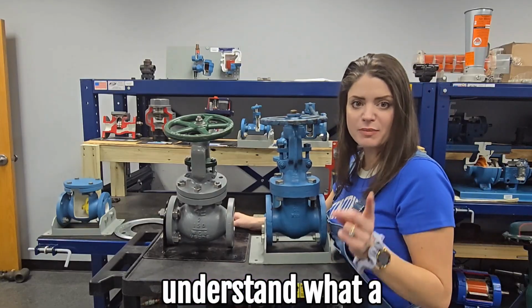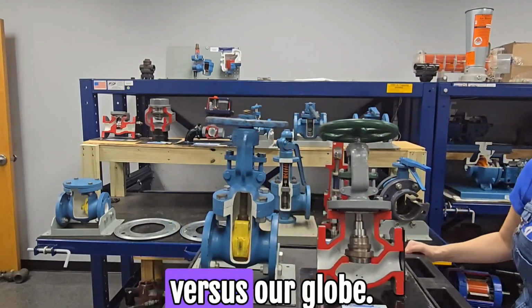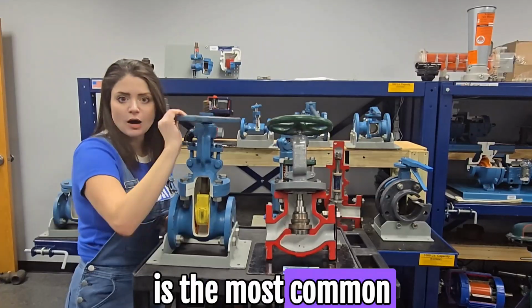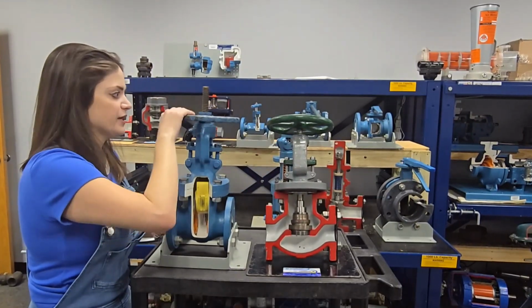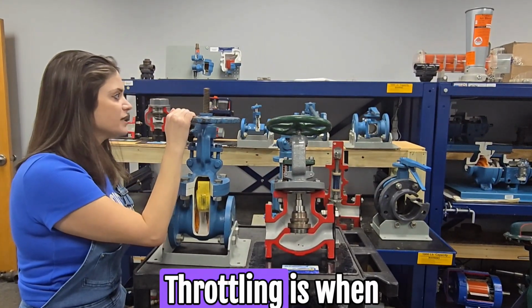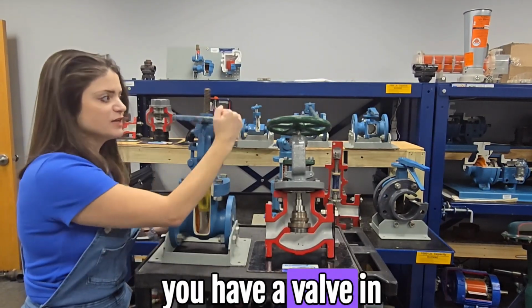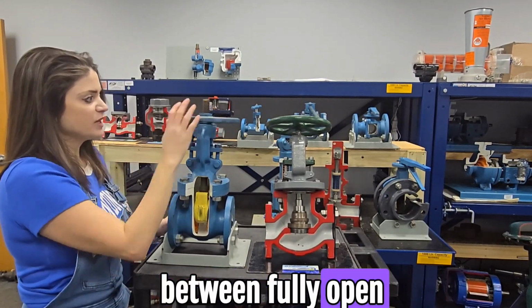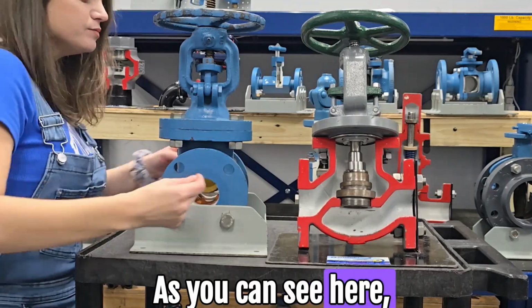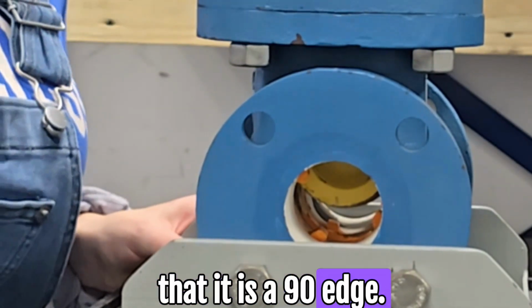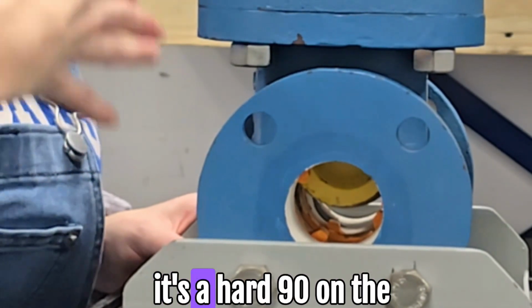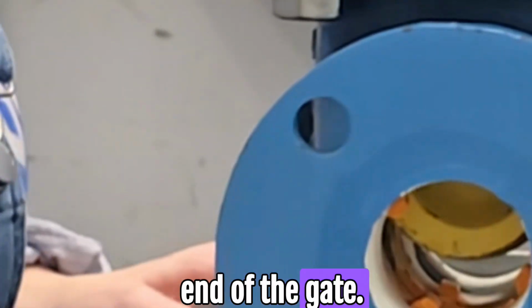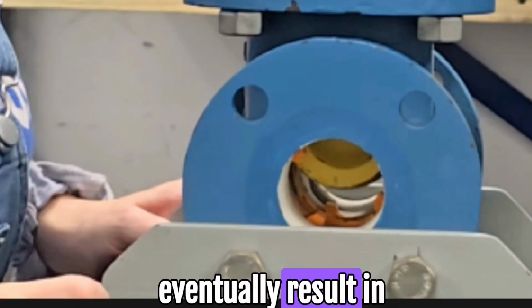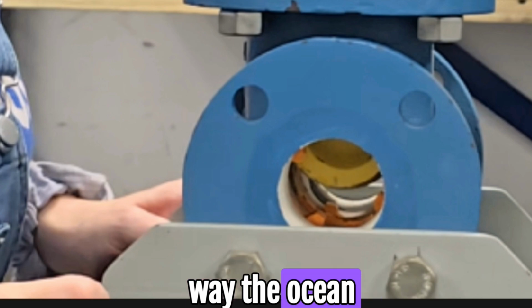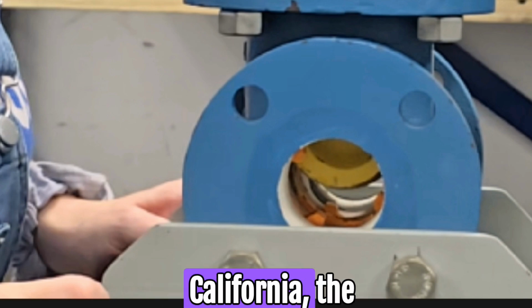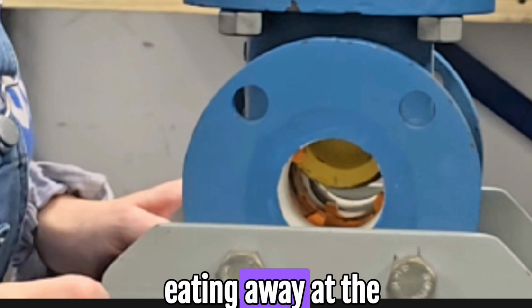So now that we understand what a beveled edge is, let's look at our gate versus our globe. Our gate valve is the most common valve for open closed position only. You do not use it for throttling. Throttling is when you have a valve in any position between fully open and fully closed. As you can see here, inside you can tell that it is a 90 edge. The edge may be curved, but it's a hard 90 on the end of the gate. If you throttle a gate valve, it will eventually result in erosion.